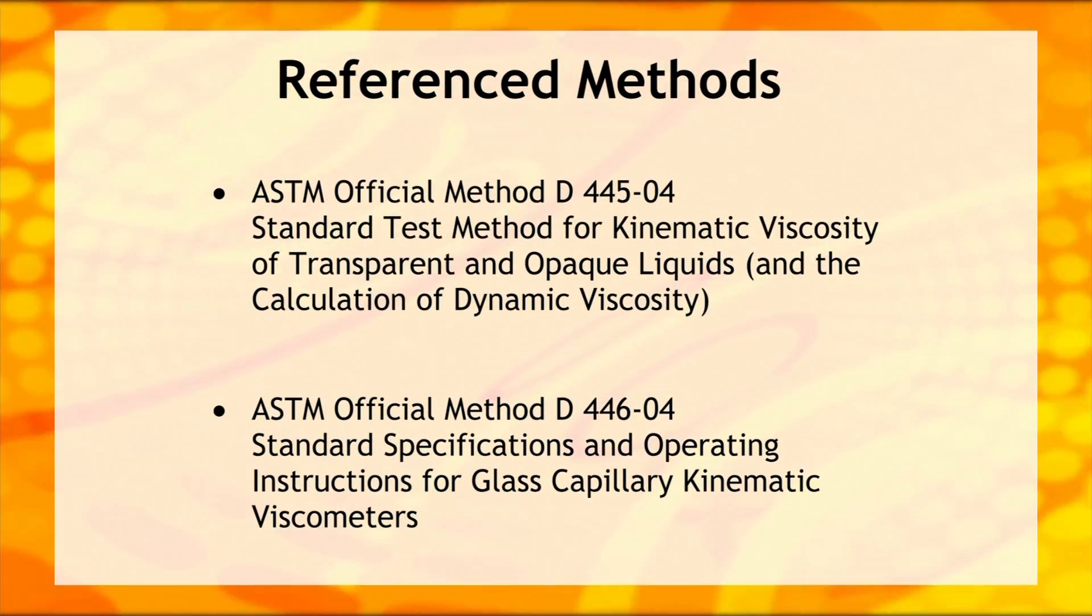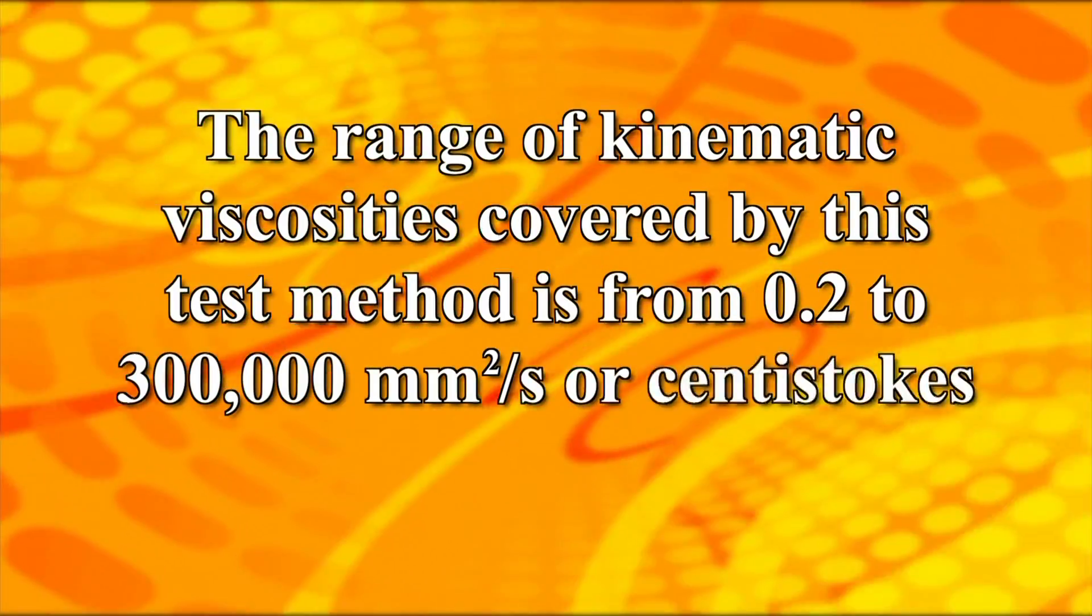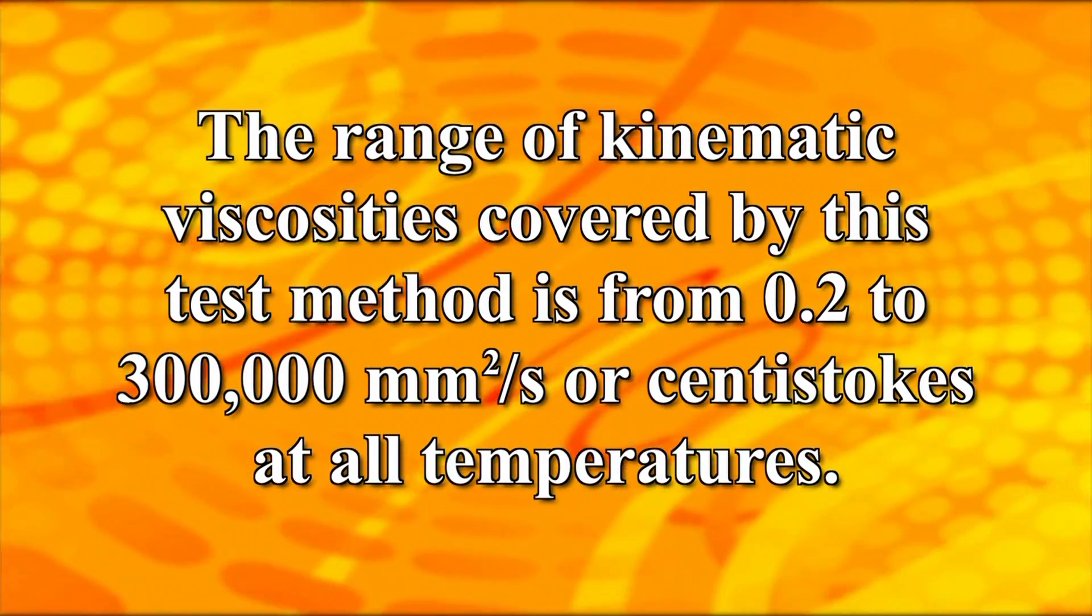The viscosity method described here is based on these official methods. The range of kinematic viscosities covered by this test method is from 0.2 to 300,000 millimeters squared per second, or centistokes, at all temperatures.